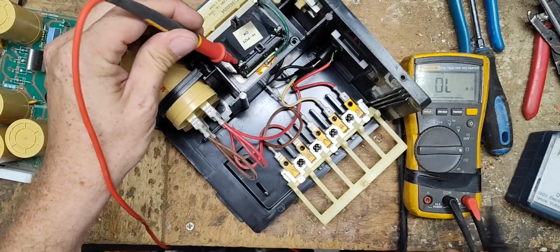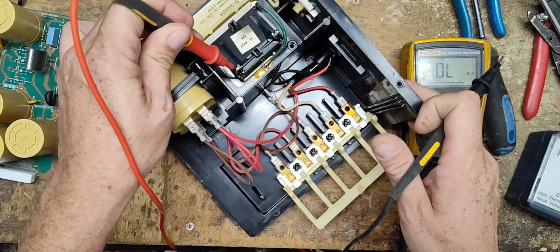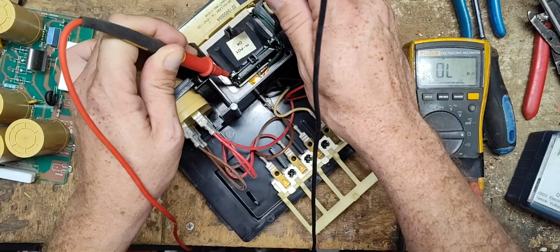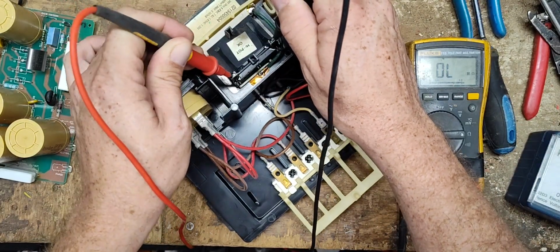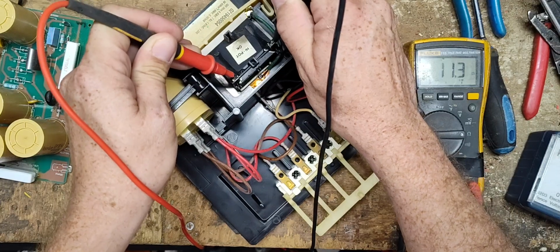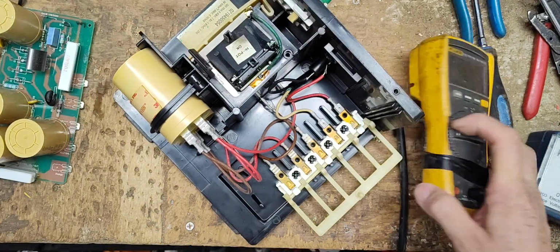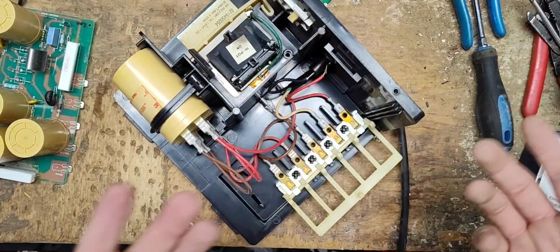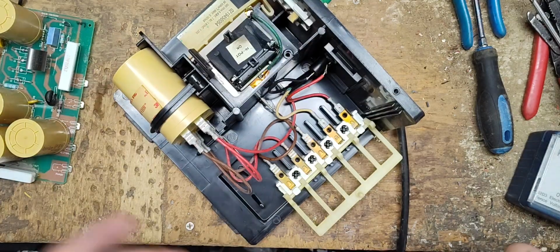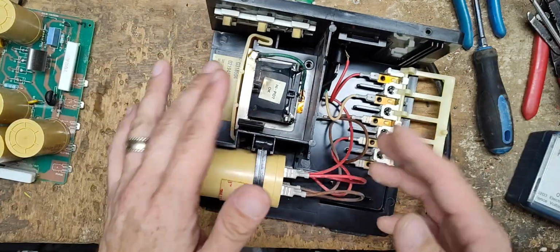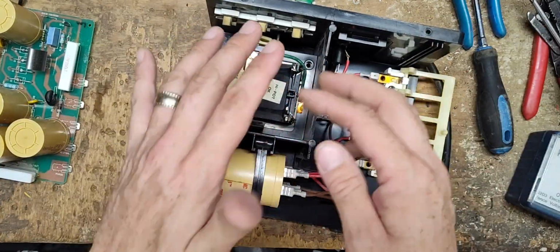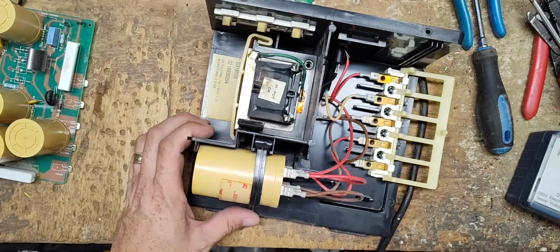The secondary side is going to vary from model to model, brand to brand. They're not universal on those, but you should get some kind of reading on it. We're getting 11 ohms, which is probably good for this one. I mean, sometimes I read 4 ohms, 2 ohms, 25, 30 ohms—they're all over the place. It just depends on the internal resistance and everything of the transformer and how it's built.